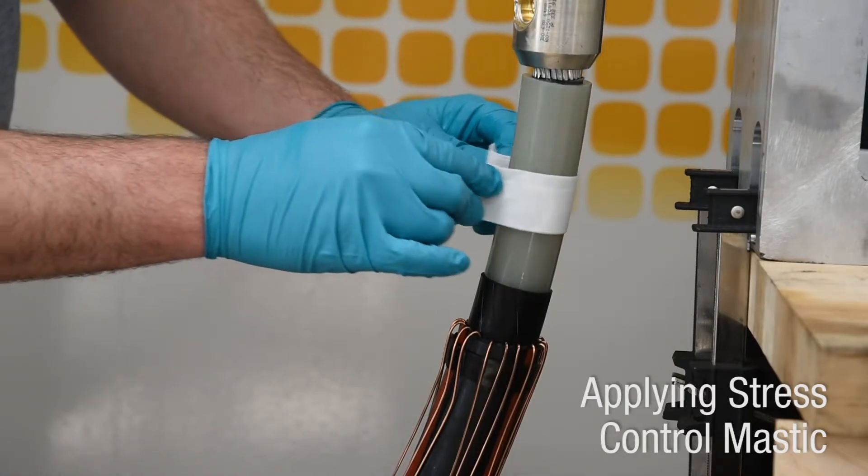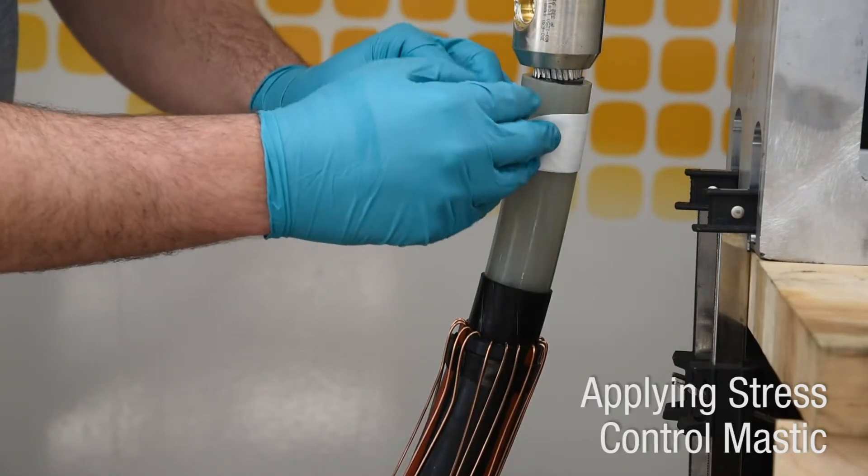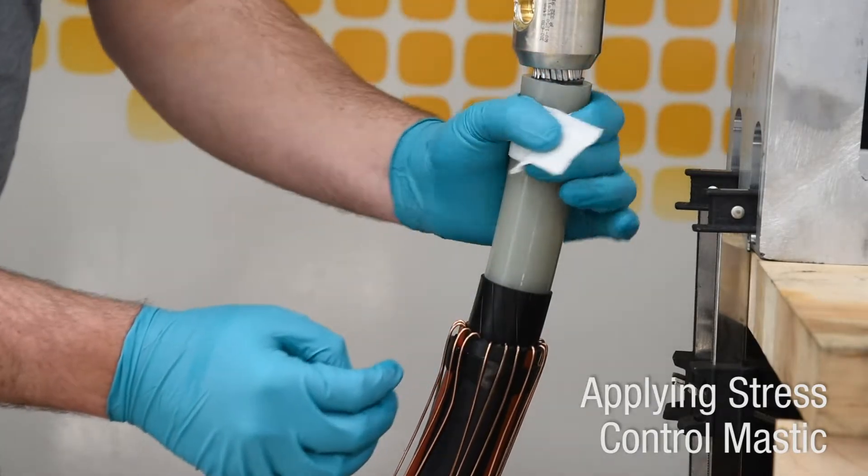Clean the cable insulation with approved wipes or solvent, wiping from the lug end of the insulation towards the semiconductor shield.